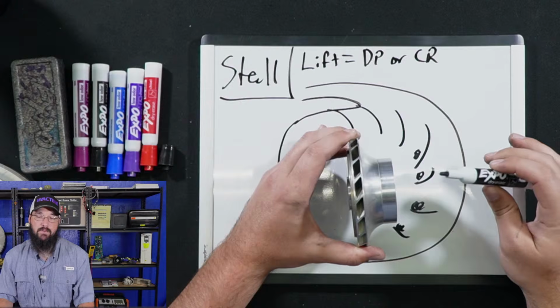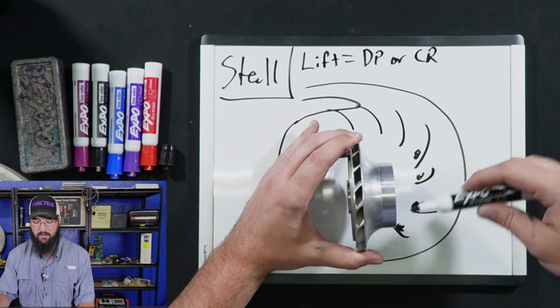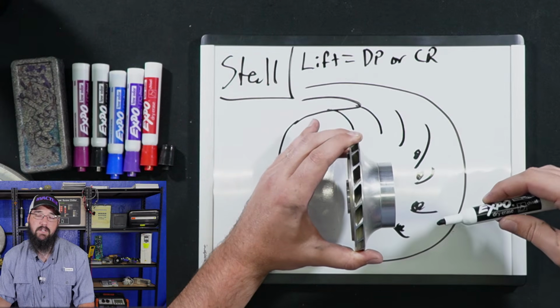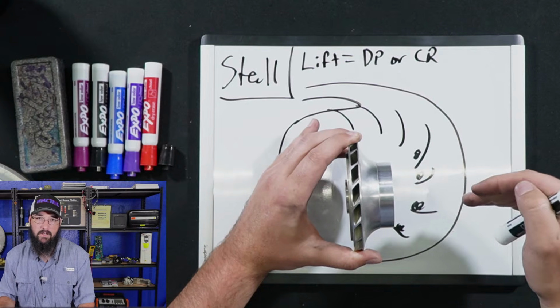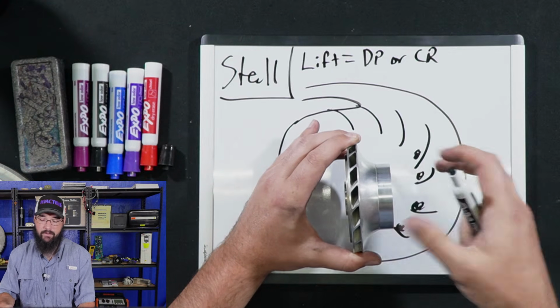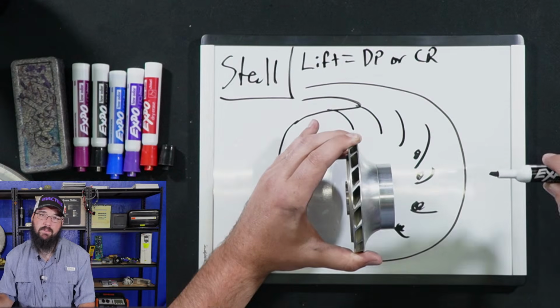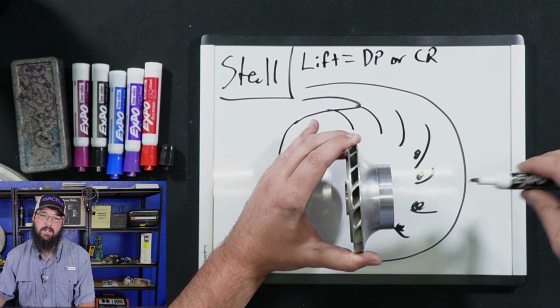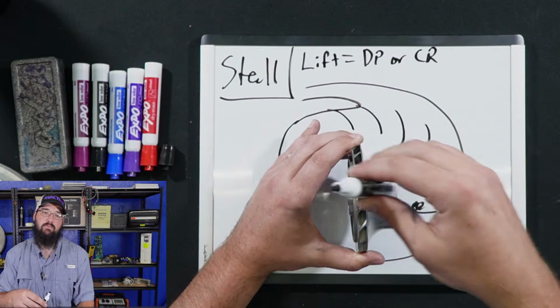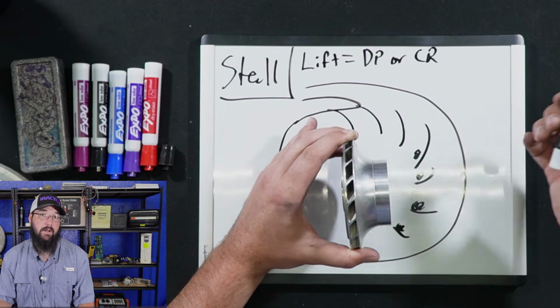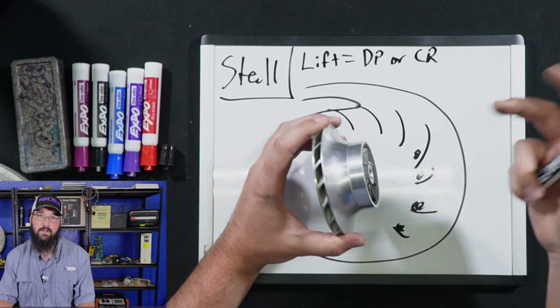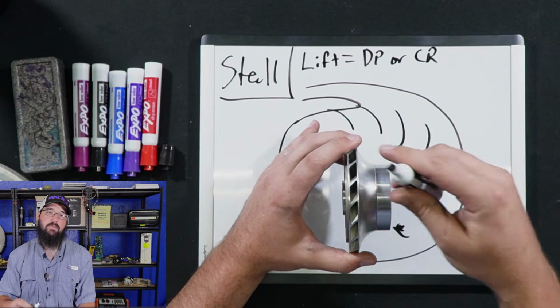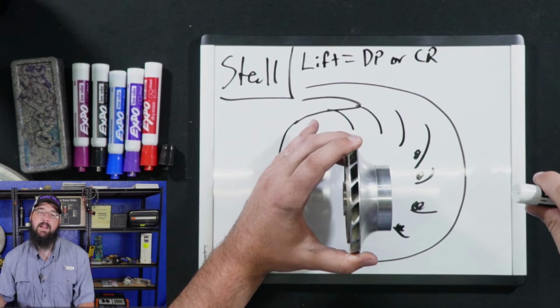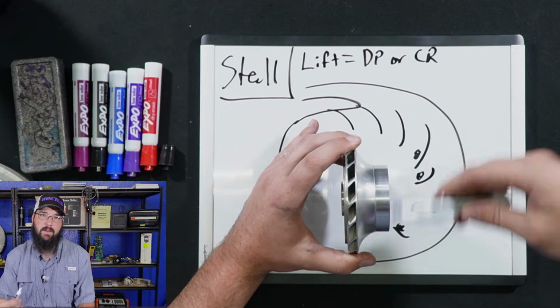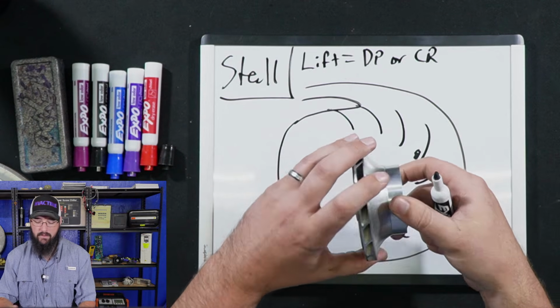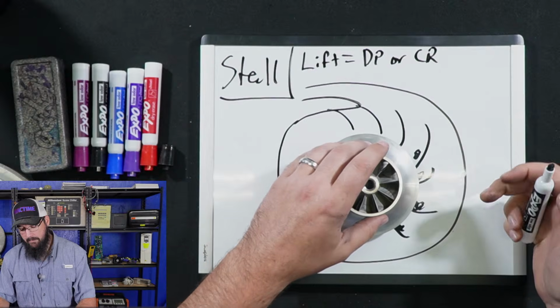This only happens momentarily because then the impeller is going to be able to reestablish, because you're going to have a sudden drop in lift when this happens here at the impeller. When that drop in lift happens, it's going to reestablish flow again, and then it's going to be able to start moving the refrigerant back in the correct direction. And depending on the conditions, it can either push itself right back into a surge and come back out, or it's going to be able to maintain that and make the corrections that it needs.